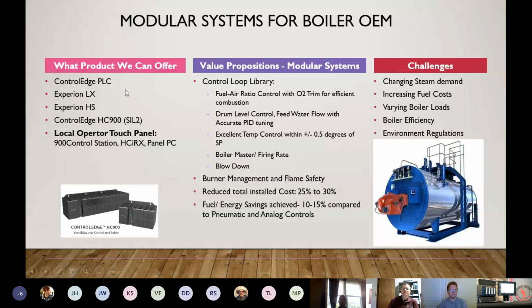So when we take a look at the HC900 used for boilers, there are other products within the family that you can use that can complement boiler control. You can use a ControlEdge PLC that we talked about at the very beginning. Experion LX and HS are Honeywell SCADA systems that you can use as a SCADA device to be able to monitor the process and do your control from a PC.